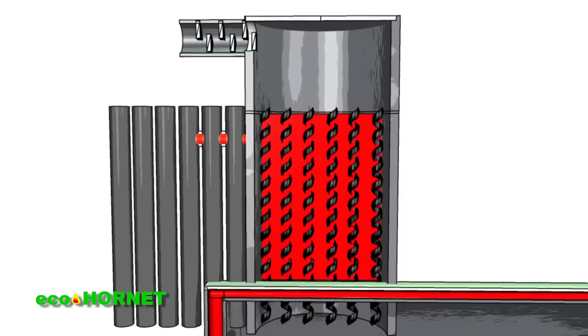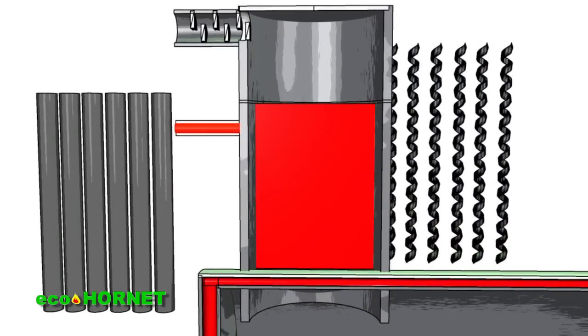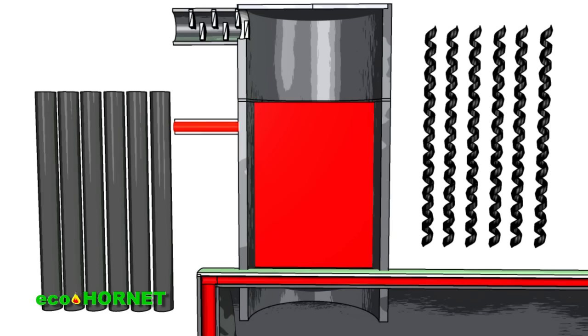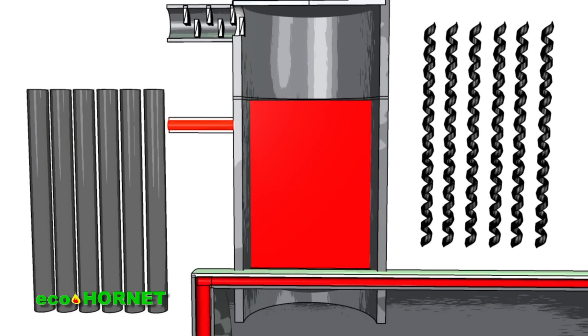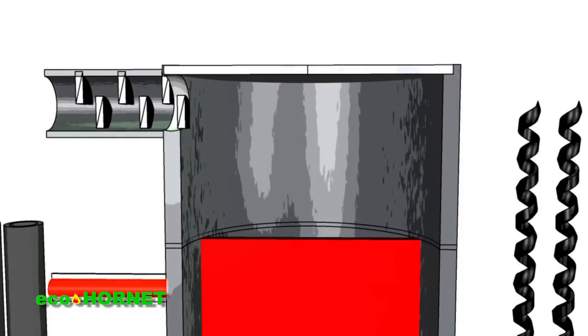Metallic spirals are inserted in the tubes for vortex generation and gas routing. Another area was designed above the pipes of the convection area which provides both uniform absorption of the gases through the pipes as well as a reduction of their speed, which allows the ash microparticles to deposit, stop, and then gravitationally return through the pipes to the ash bin.